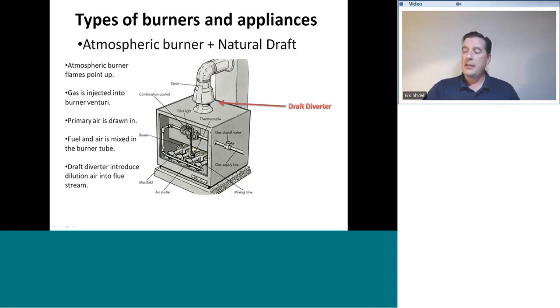Here's a hot tip, especially on boilers. Boilers generally tend to be larger BTU input than furnaces do. They need a lot of combustion air, and they very often don't have it. If above the burner area, in this area right here, you see a big dark stain, looks like the paint has been overheated, looks like there may have been a fire there, you might think to yourself, well, that makes sense. That's natural because there's a big fire right there. It makes sense that that would be heat damaged.